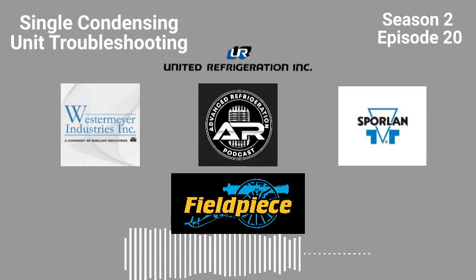Now it's almost impossible to run new HE cases on condensing units without some sort of capacity control. And when you start throwing pulse valves in there, there's no point in putting that in. All you're doing is making the problem worse. You're better off with the standard expansion valve at that point, because that pulse valve is never going to do its job. It's never going to be able to run long enough, because the condensing unit's never going to have the right operating parameters. It's never going to be in that operating range. It's at the highest ambient it can be, like what the design was. Even at that, if you were running it at 107, like yours said, I guarantee the suction pressure would probably still be low.